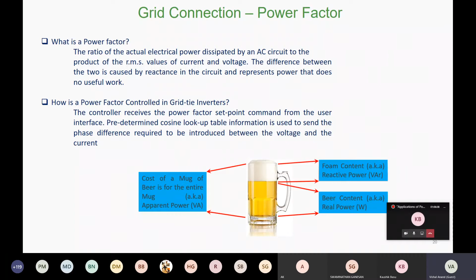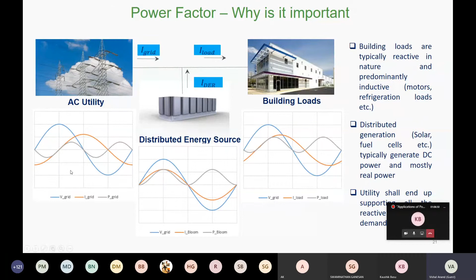So why is it important? This is an example of how the power factor impacts the tariffs. This is a building load. Normally, all building loads will usually be reactive in nature, so you can see the current here is reactive. And the distributed energy resource, in this case a fuel cell, could be solar, could be wind, anything, but most distributed energy resources always generate power in phase with the voltage. So all the real power consumed by the load is supported by the distributed energy resource, whereas the utility ends up doing all the dirty work and supports the reactive power. The problem is that the utility doesn't like this, because they don't get to bill the customer for anything, and it requires the DER to support the reactive power. So this is very important.